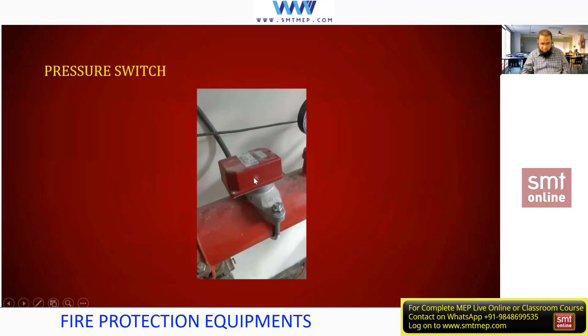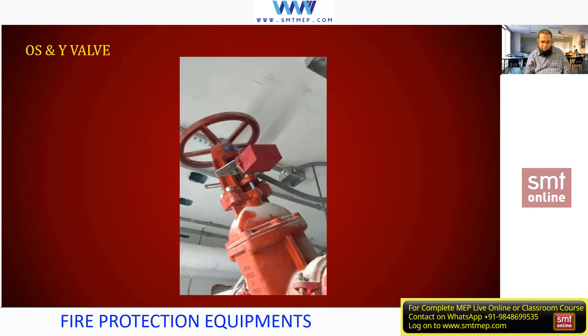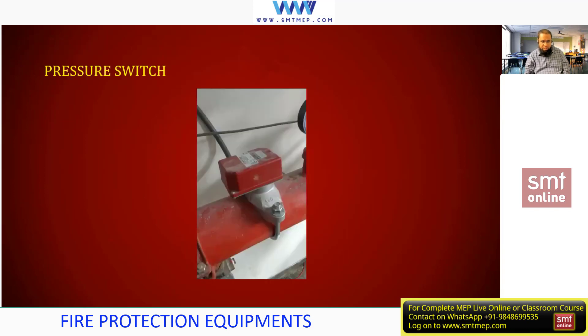In the same zone control valve assembly, the pressure switch is also here. Flow switch and pressure switch are different components. The flow switch you'll find near the pump, while the pressure switch you'll find at each zone control valve assembly. The purpose: whenever there is a change in pressure or when flow starts, this will give a signal to the control system so that the control system can activate the equipment.